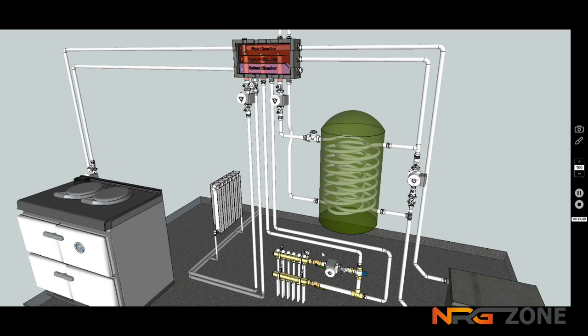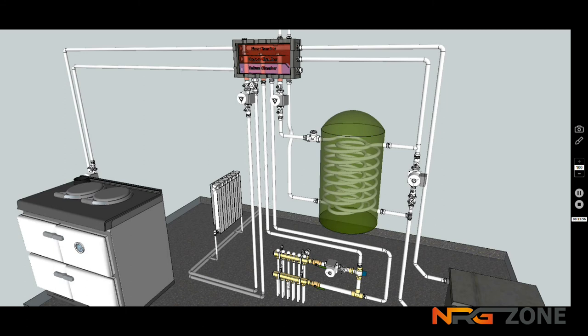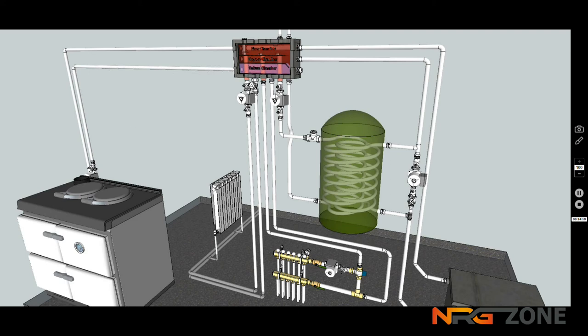But if the water in the floor starts to lose too much heat and starts to get cold, the mixing valve will start to operate, and will open this port, and close the bypass port. Now this pump will start to pull hot water down, mixed with some of the return water, and again get the temperature level to the perfect height, which should be monitored on a gauge at the manifold. Cold water coming back from the underfloor system, of course, will go back up, and again be the coldest water that would go back to the condensing cooker, making that cooker work all the better again.